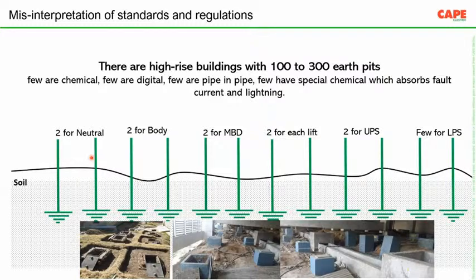So there are high-rise buildings, especially office complexes and even data centers in India. Data centers in India have 100 to 300 earth pits all around the building. Actually, one building requires only one earth pit. And why do we have 300 earth pits? Actually, by installing more and more earth pits, the problems are becoming higher and higher. And then we have the habit of using chemical earth pit, digital earth pit, pipe-in-pipe earth pit, and so many most modern names which we call these earth pits.